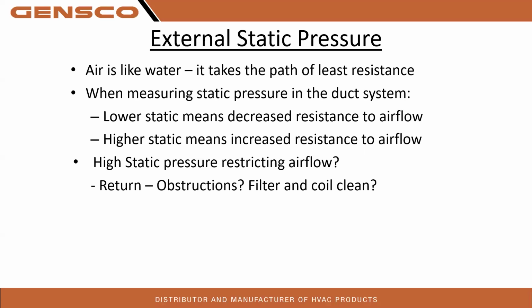Coil clean, that's evaporator coils, right? So again, I hear a lot, yeah, they're clean. Well, sometimes you can't see that. The only clean coil is the coil that you just cleaned. I hear a lot, yeah, they cleaned it last year. How do we know, right? A good thorough cleaning, I mean, you can pull that thing out, reclaim the refrigerant, or try to get in there and clean it with detergents and whatnot, but it can get messy.